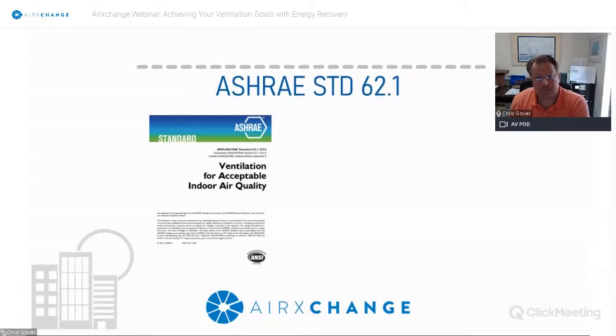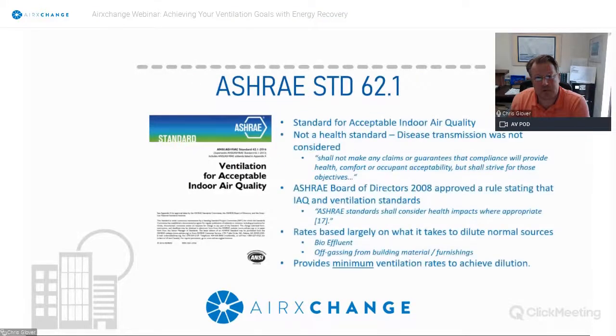I should also state that ASHRAE Standard 62.1 is not a health standard. It means that disease transmission was not considered when developing the rates. It strives to provide guidance for health, comfort, and occupant acceptability, but once again, it doesn't guarantee it.